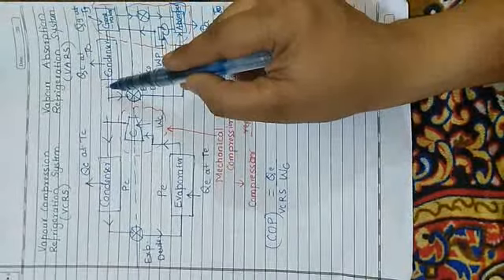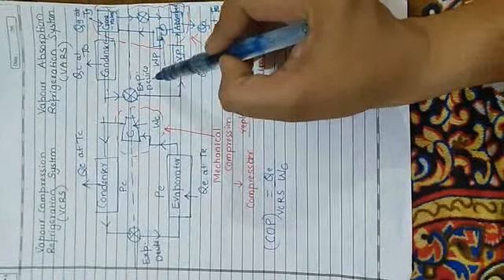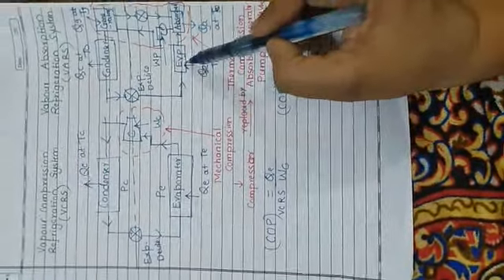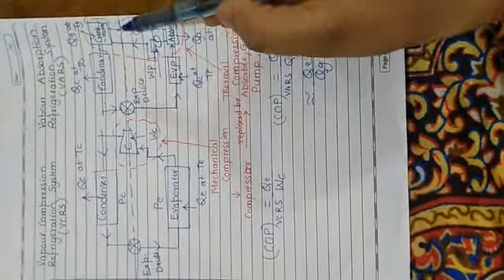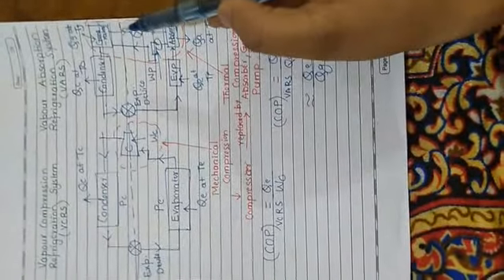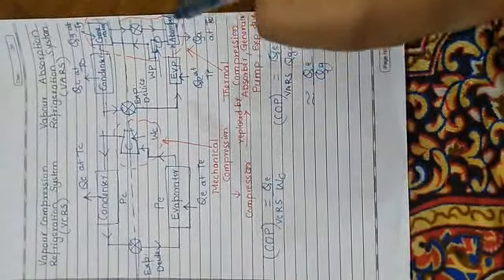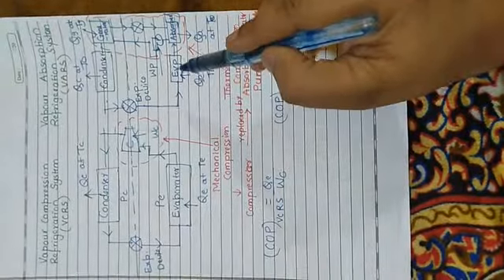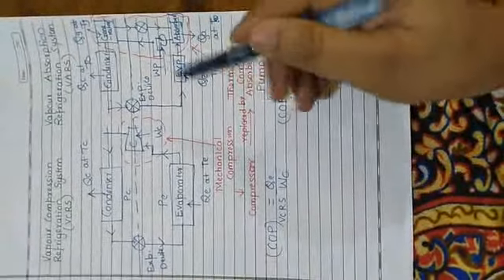Then the liquid refrigerant is throttled by an expansion device to the evaporator pressure. At the generator side, the solution which is weak in refrigerant is throttled back to the absorber, where it again becomes rich by absorbing the refrigerant vapors coming out of the evaporator.